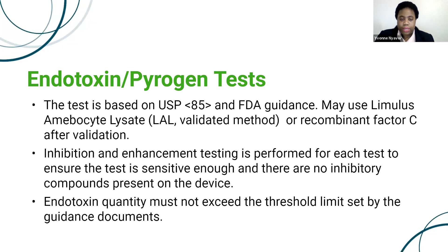Okay, so at Boston Analytical, we do offer all three different types of LAL tests. And then the endotoxin quantity limits, again, depend on the device type. So for example, for devices that come into contact with the cerebrospinal fluid, the limit is extremely low as compared to devices that aren't really in direct contact with CSF. And so sometimes you have limits as low as 0.006 EU per device. And in some cases, you have as high as 20 EU per device. So it's important to determine that limit for your device, specifically depending on what class it is, and we're able to, of course, offer some guidance on this if that is a need.